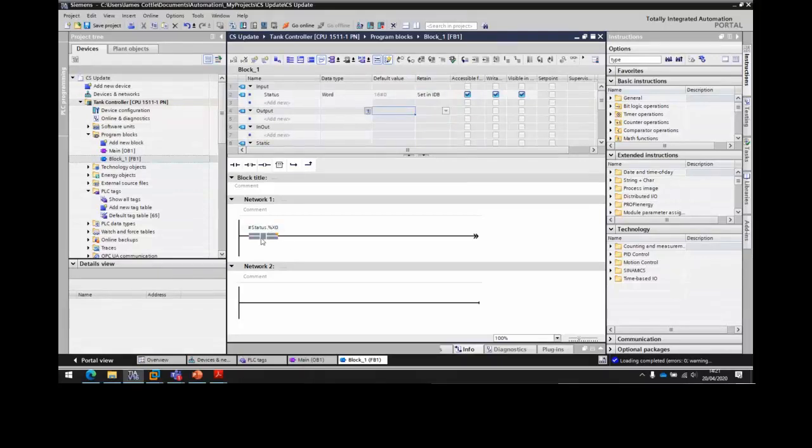So what I just showed you here was called slice access, and what I'm going to show you now is AT construct. So our input here could be a status word. So this is the status word. Let's pretend it's still from my drive. And maybe within my status word, I then have those different booleans. So to break it down with AT construct, I can define a new tag underneath status word, which we'll just call status for convenience. And then we just type AT, which gives us access to the AT construct.